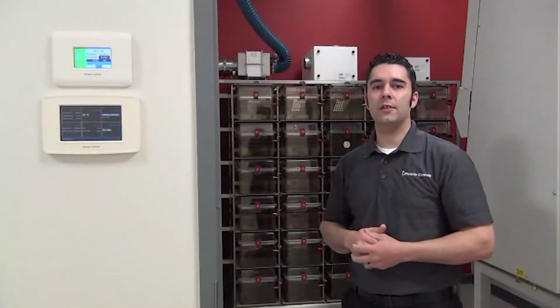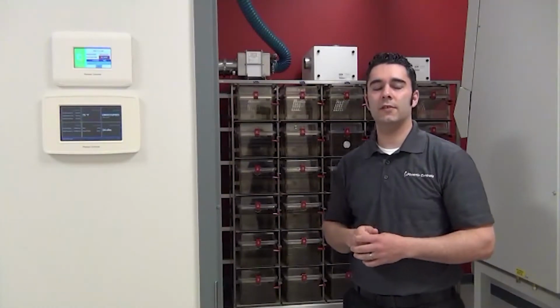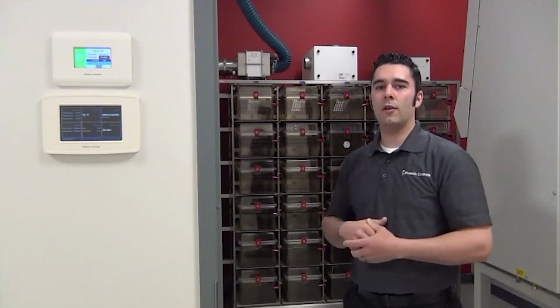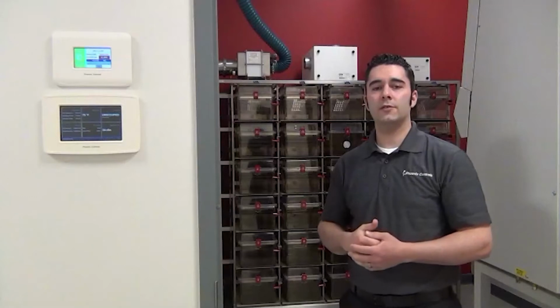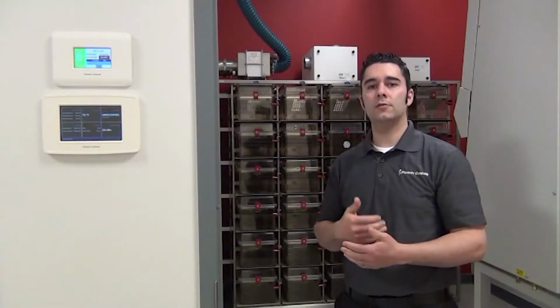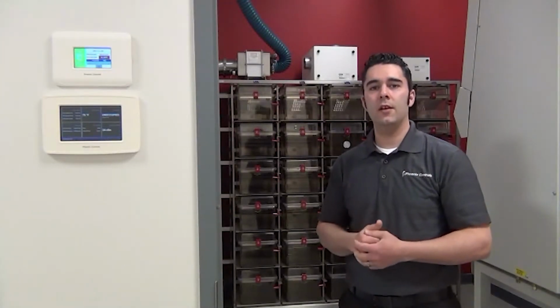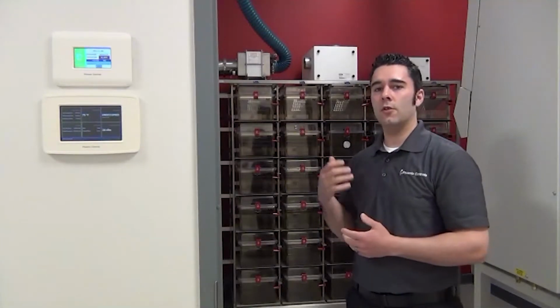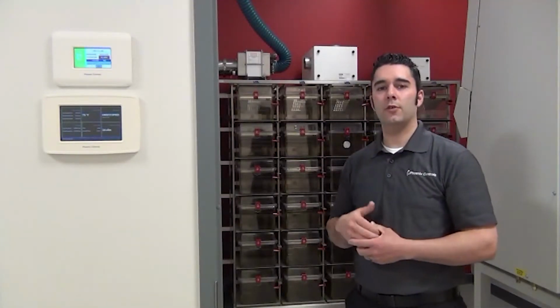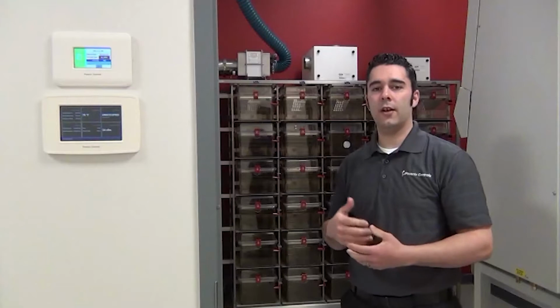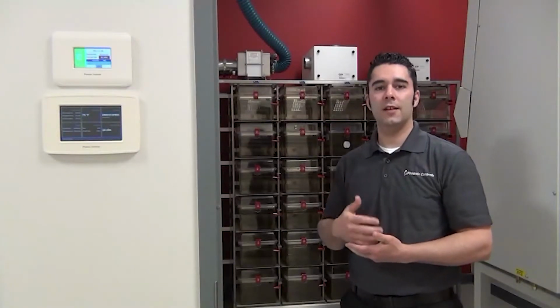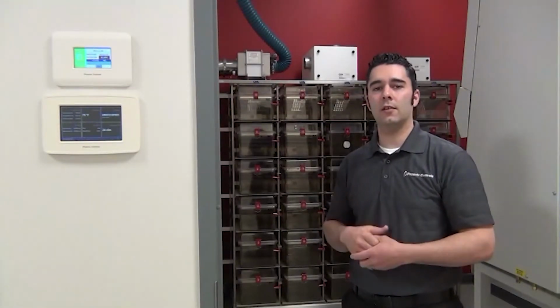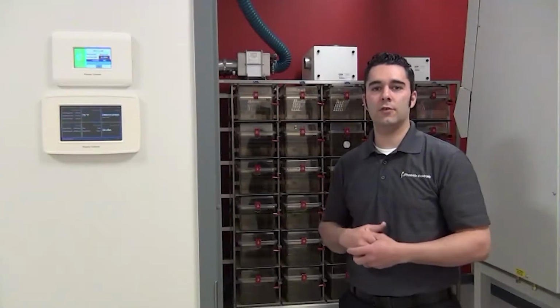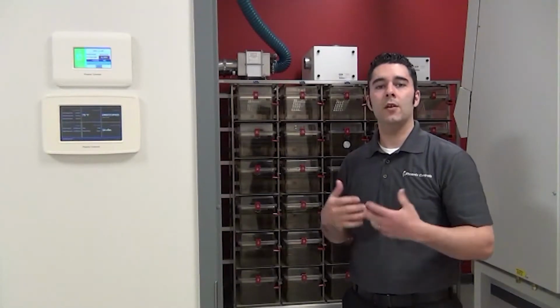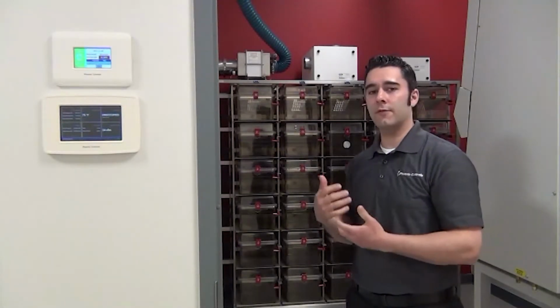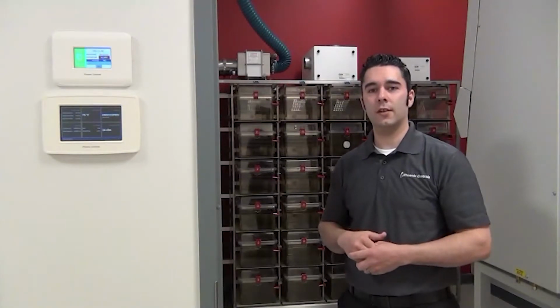This makes it a lot easier for people to install these in the field, and they work very well when you're using them with exhaust situations because, again, our valves don't get dirty with the dust and the lint building up on the valves. So in this particular environment, this would be great for a cage rack because you don't have to worry about the dust and the dander from the animals in their bedding getting into the sensors in a traditional product and clogging them up. We don't have sensors in our product, so therefore the Phoenix Controls valve works great in a cage rack.